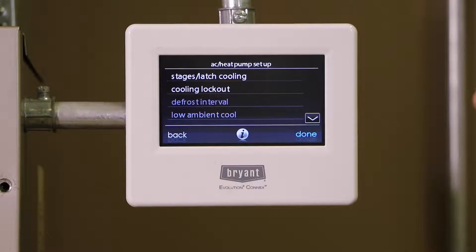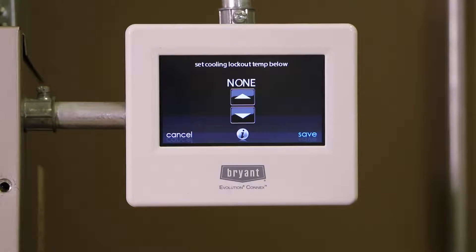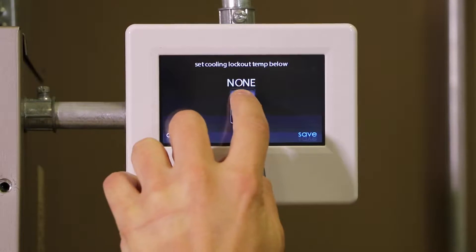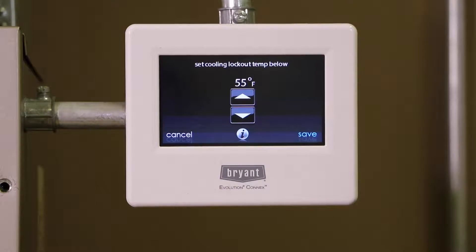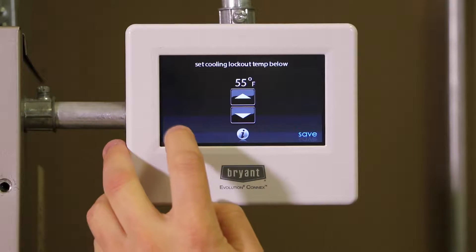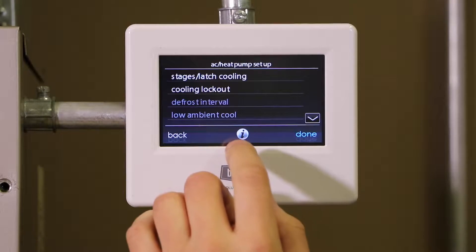The next choice we have on here is cooling lockout. If I click on that I only have the choices of none, 45 degrees, 50 degrees, or 55 degrees, and that will disable compressor cooling below a certain outdoor air temperature. Sometimes you may want to do that so people don't accidentally go into cooling on auto mode when they really don't want to. In my case I'm going to hit cancel and go back.